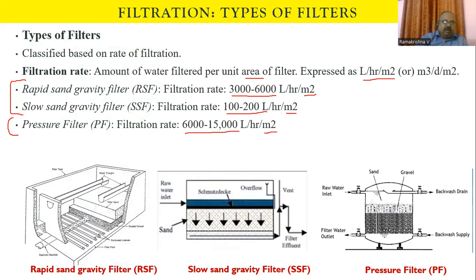Because a pressure filter can handle more water per unit area, its sizing is compact — it is a small cylindrical unit. A slow sand filter, handling very little water per unit area, occupies a relatively large area. The rapid sand gravity filter occupies a medium area between the pressure filter and the slow sand gravity filter.